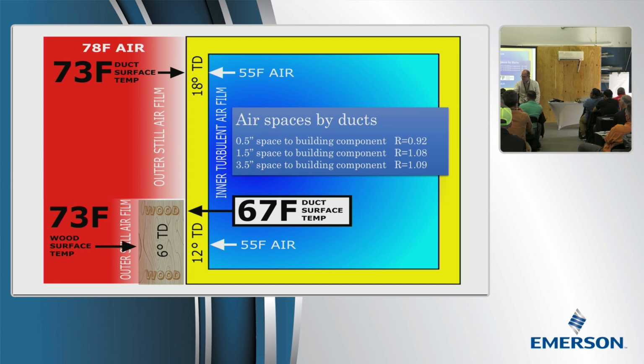North Carolina? Yeah, I can see that. That's exactly what we're talking about. As a matter of fact, I have a slide of exactly that. What he's talking about is ducts just laying on the ceiling. It's not even that uncommon. Did you ever check the temperature between the sheetrock and the insulation, and above the insulation in the attic? It's hotter when you get to the sheetrock than it is on top. And you're compressing your insulation on your flex, so you're losing your R value.